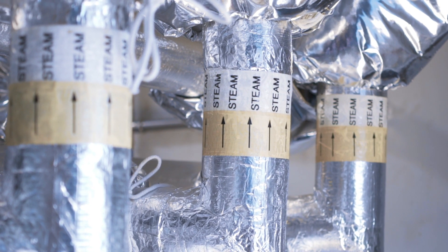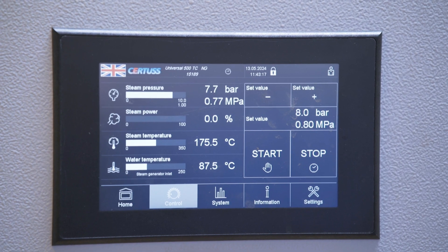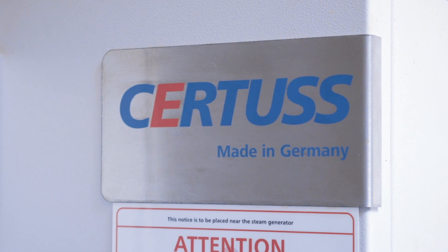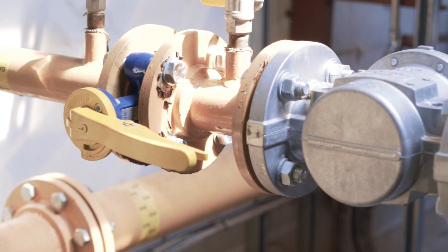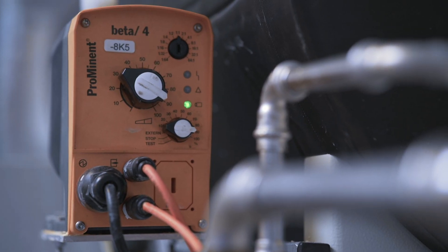There's a lot less maintenance involved with them — they're fully automatic, they run themselves. Although the package boilers kind of ran themselves, they didn't need somebody watching them all the time. And when they came for the yearly inspections there was quite a lot of work cleaning the flues out and the tubes. Whereas your engineers come and do the servicing on them now and the insurance inspector just has to see the coil pressurised and test the safeties and the gauges, and that's it really.